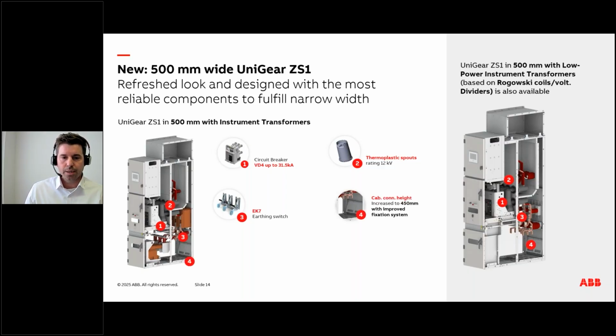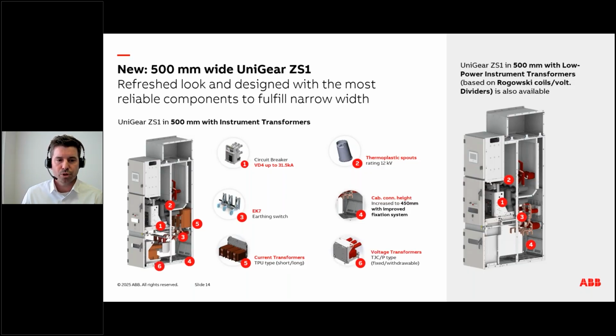Then a key highlight of the panel design is the cable connection. The cable connection height is 450 millimeters. It allows us to connect up to 3 cables per phase. When we look into the current transformers, they are typically installed in the cable compartment, and voltage transformers are installed in the front of the cable compartment part of the panel, either in fixed or removable design.